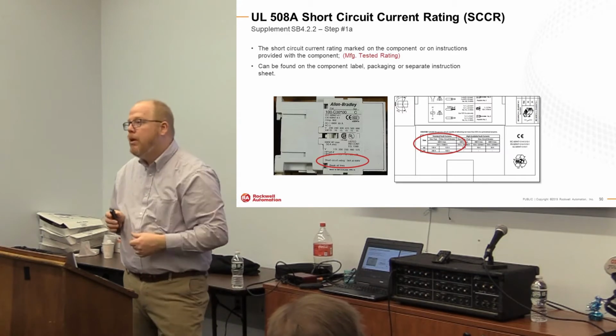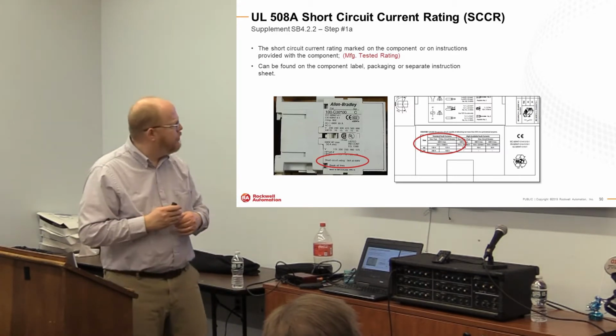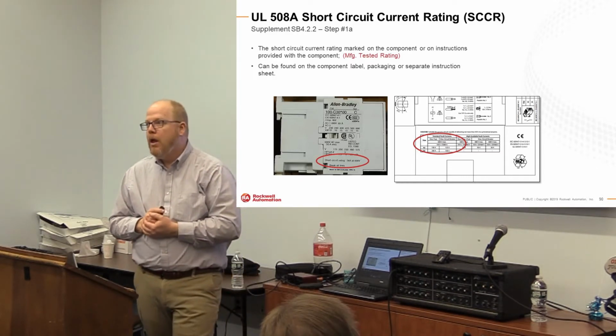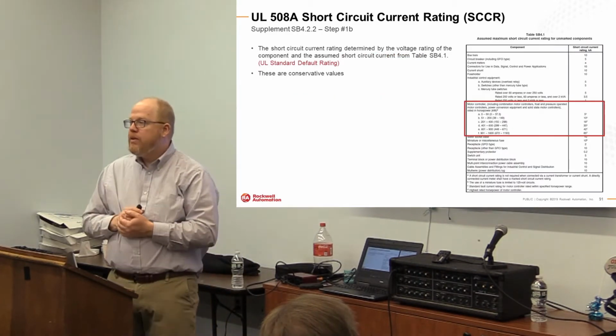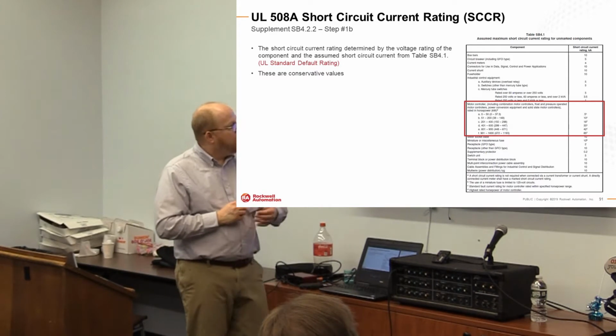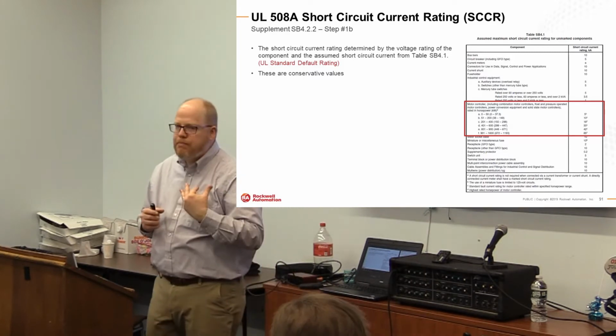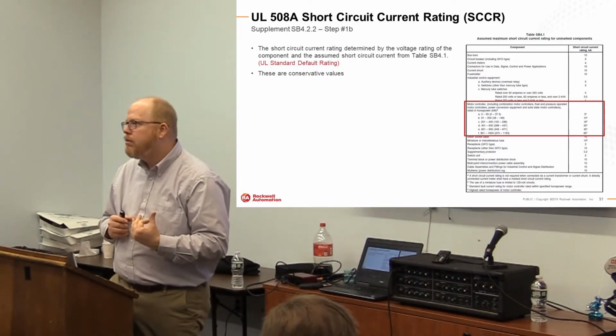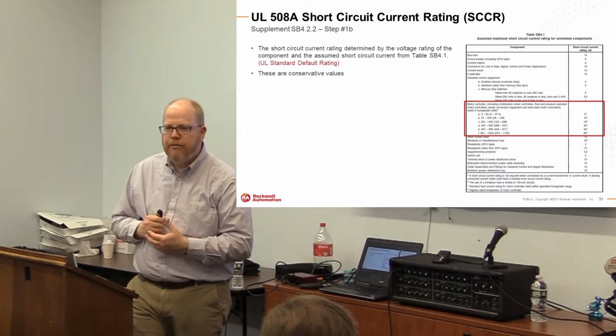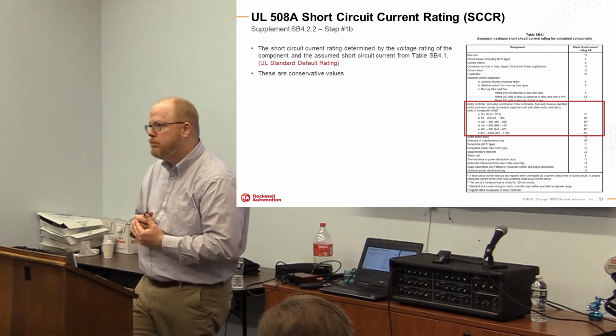Here's an example of a component. I know it's hard to read from the slide deck, but it just gives an individual short circuit rating. Here's an example of the table in SB 4.1. You can see here, for example, motor controller. Most often, you're going to see ratings by default of 5 or 10 kA, predominantly for most of your power components.